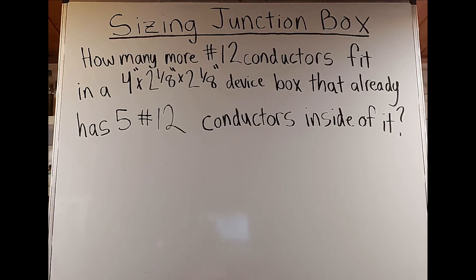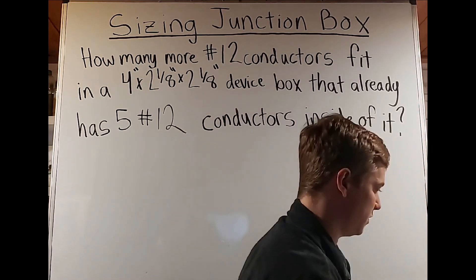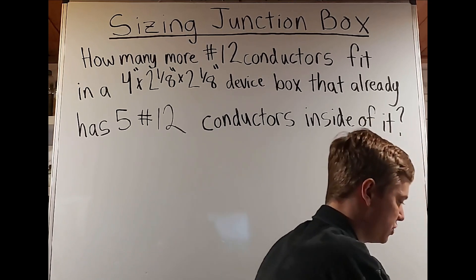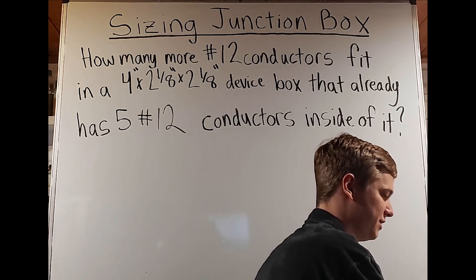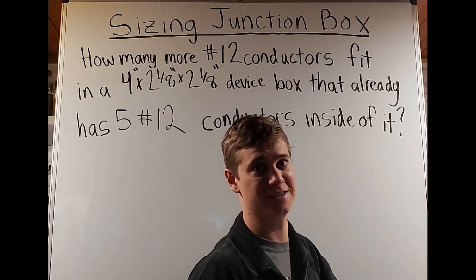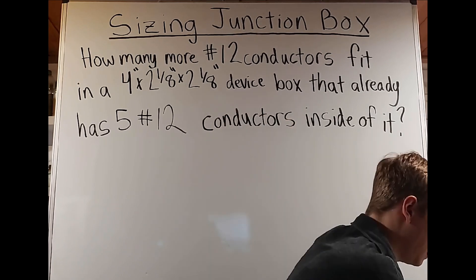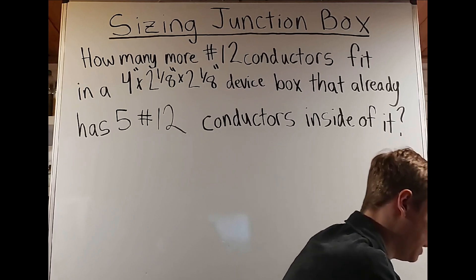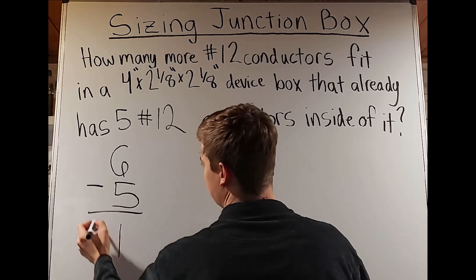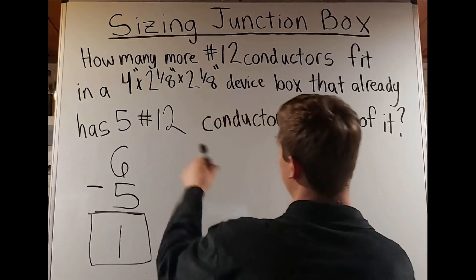Next: how many more number-12 conductors fit in a four by two-and-one-eighth by two-and-one-eighth inch device box that already has five number-12 conductors inside? We go to Table 314.16A and find that device box size — note that the second and third numbers are repeating while the first differs. Looking under 12-gauge conductors, we see six is the maximum. We already have five, so we can fit one more additional number-12 conductor in this device box.